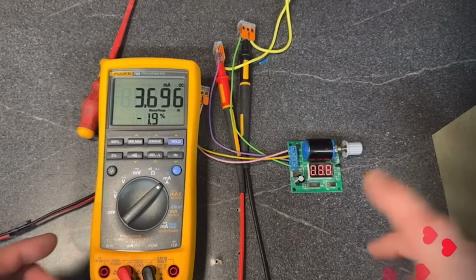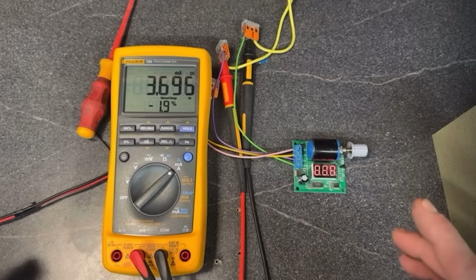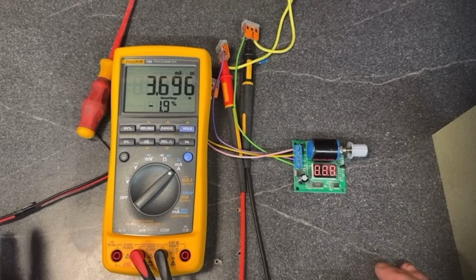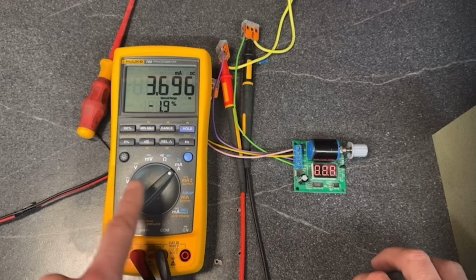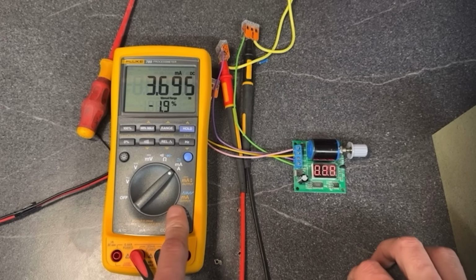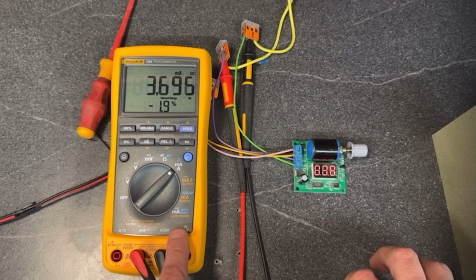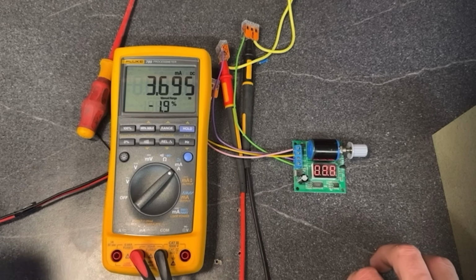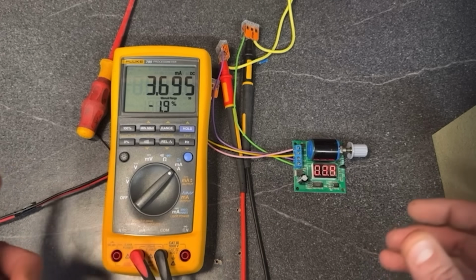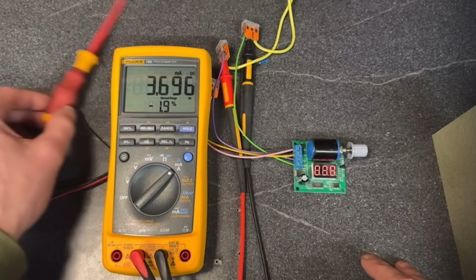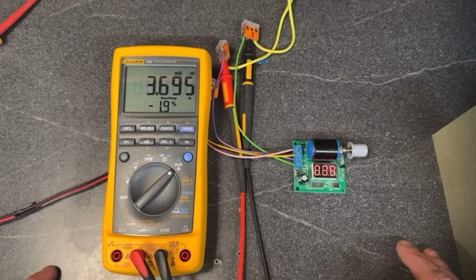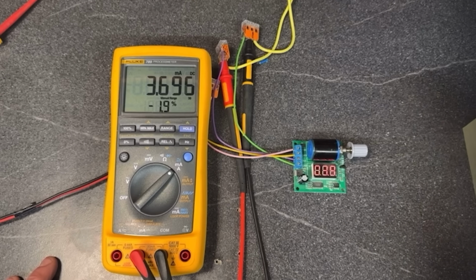These are the other 2 process devices I have for measuring 4 to 20 milliamps, and one of them is this one, a Fluke 789. I'm going to show you that shortly. The problem with the Fluke 789 is it doesn't do 1 to 10 volt - I've got another test rig that does that. You don't come across 1 to 10 volt much anymore because it's out the arc, although HVAC people still use it, and lighting controls still use it because it's cheap as chips.